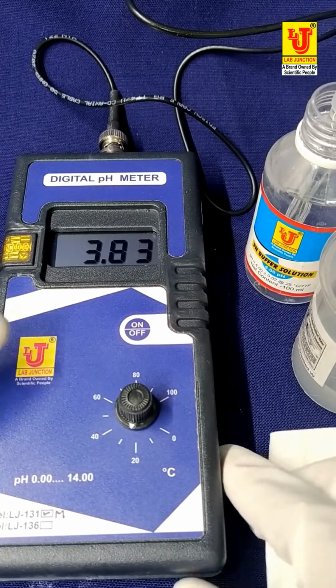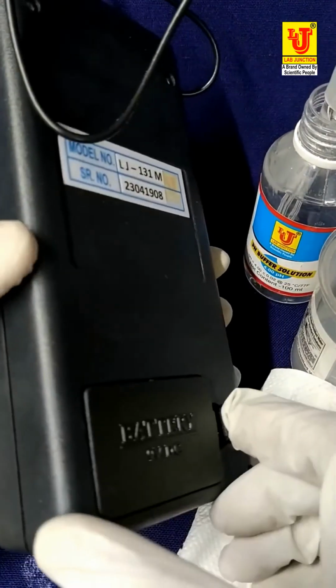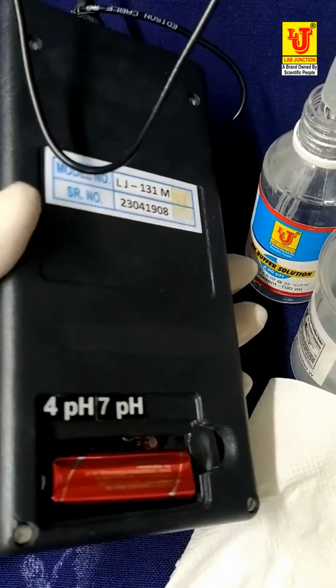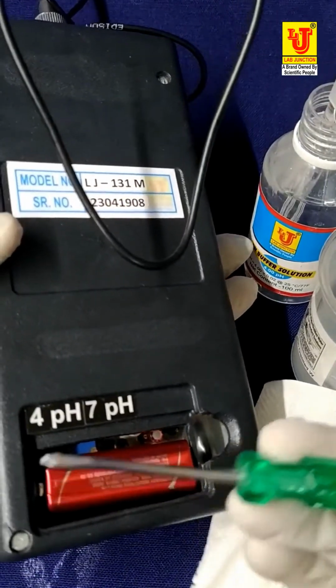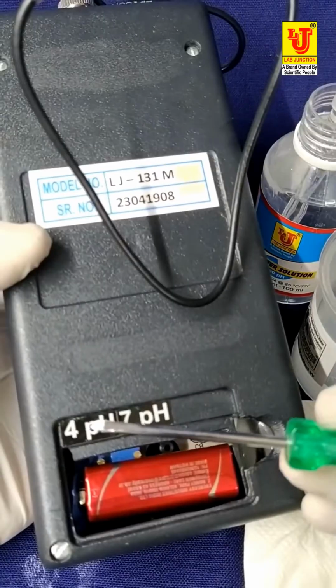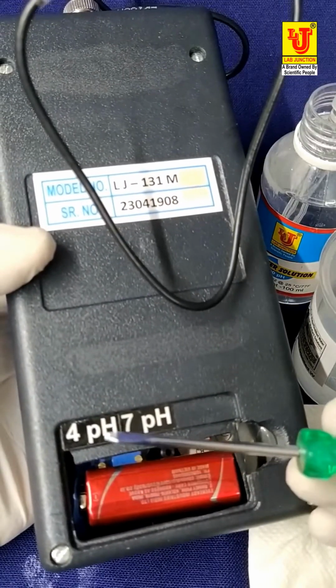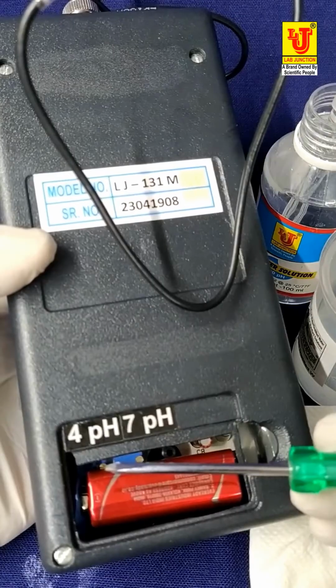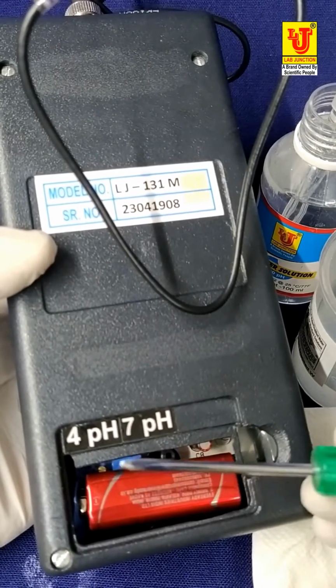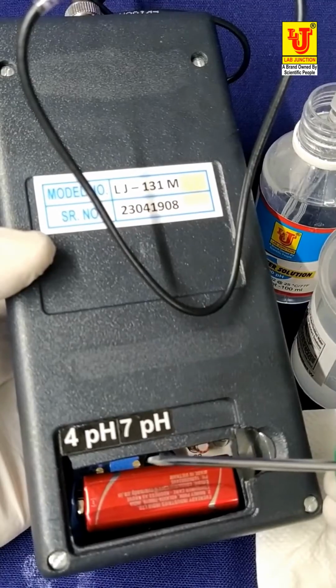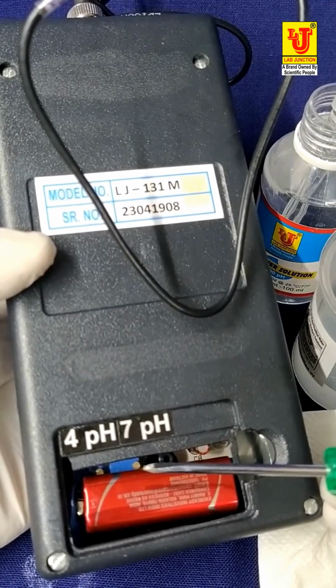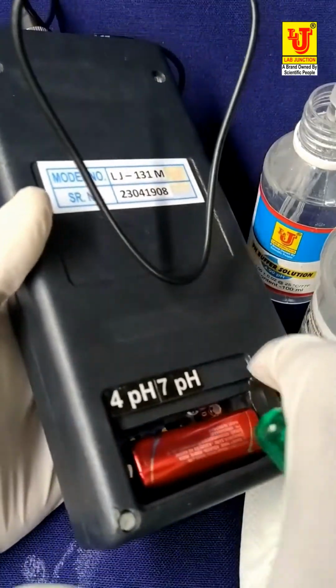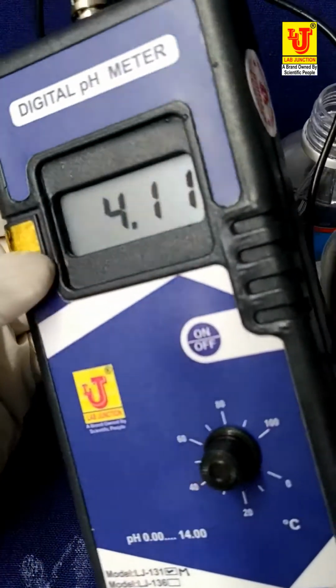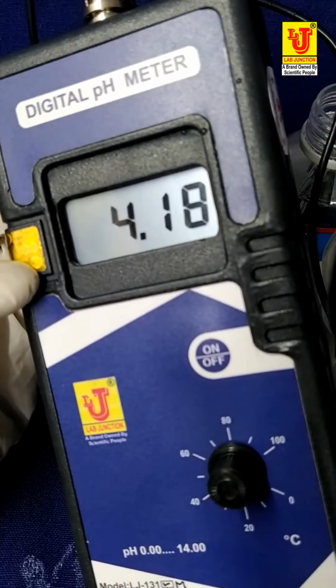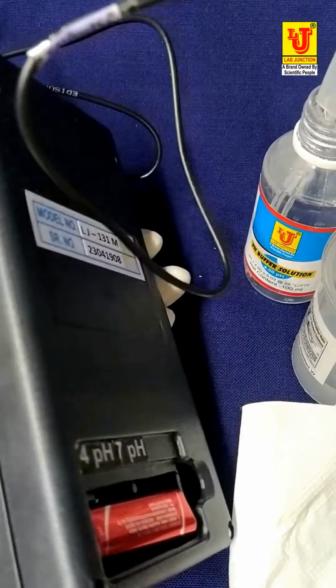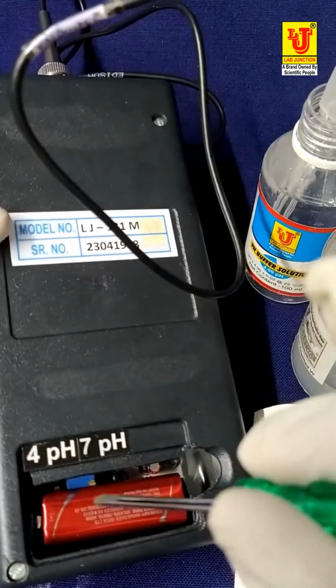Suppose I have to reset the pH again. Open this compartment. There are two trim pots. The first one is for 4 pH. You have to set this screw of 4 pH with the screwdriver for pH setting, and for 7 pH you have to set this trim pot screw. Suppose my 4 pH does not read correctly, I am setting it like this from 4.